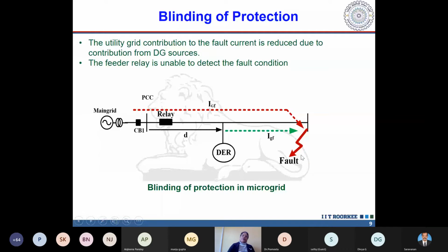10 ampere earlier was contributed by only the grid, but now due to the presence of DER, this 10 ampere is going to be divided into two sources. Let us say 8 ampere is contributed by the main grid, and 2 ampere is contributed by the DER. So due to this division, at this relay location the relay will see 8 ampere instead of 10 ampere. That means the current magnitude will reduce at this location due to the presence of DER.